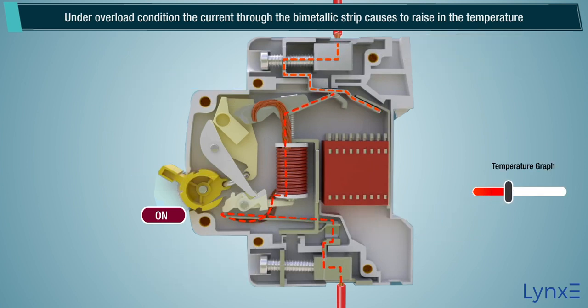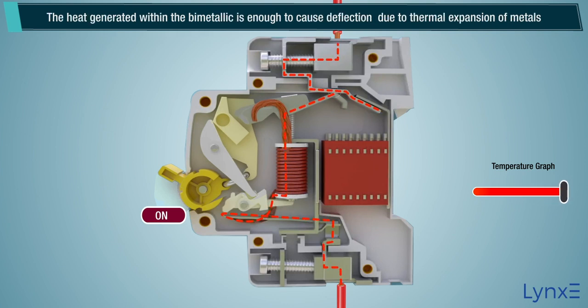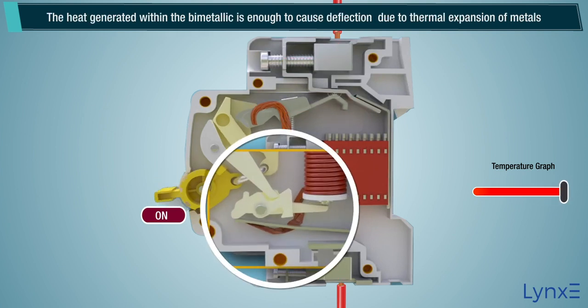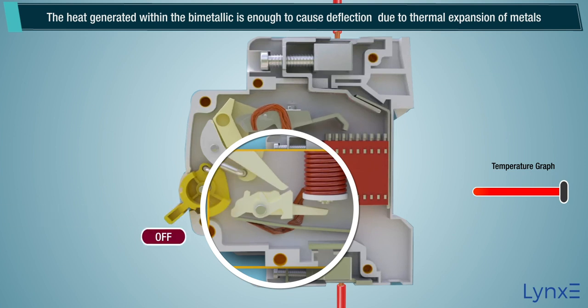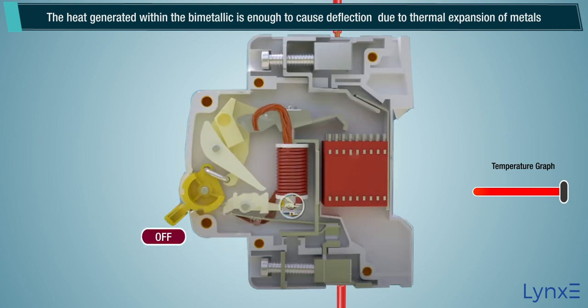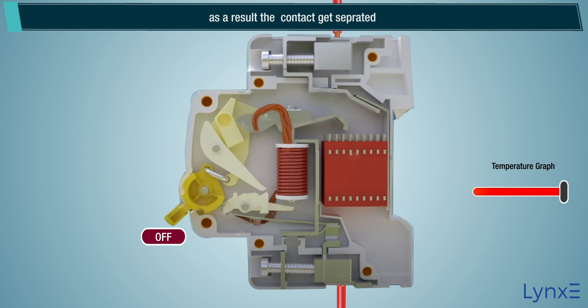Under overload condition, the current through the bimetallic strip causes a rise in temperature. The heat generated within the bimetallic strip is enough to cause deflection due to thermal expansion of metals. As a result, the contact gets separated.